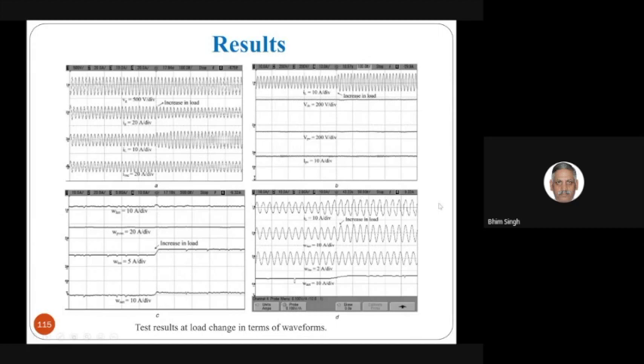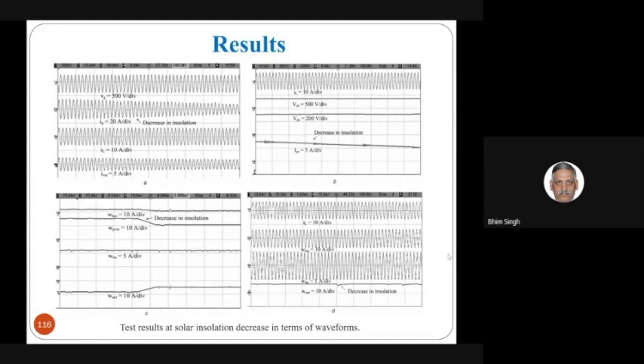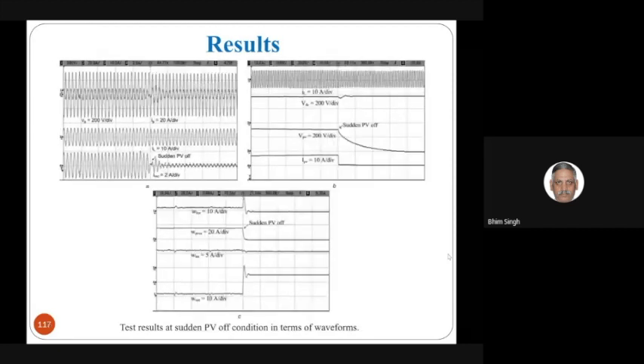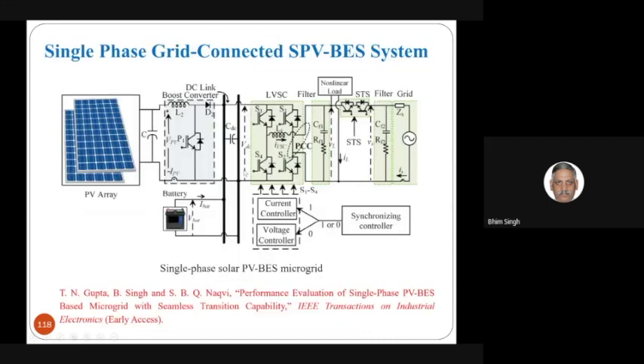When the load is increased, you will find the control signal changes, and less power flows to the grid because the power generation is constant. These are typically cases when the solar insolation level is decreasing, and this is how the system meets the requirement. Then, suddenly at night when there is no PV generation, the system still works very well as an active system. The converter is able to operate and compensate the load. Now, coming to another interesting part.